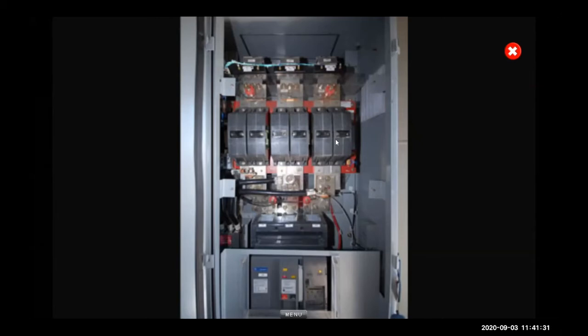And it also allows you right there, that's where they open. So if I want to turn this entire wind turbine off and not have it connected to the grid, this is where you're going to do it, guys. You're going to pull the big master switch and lock it out. That'll be the first point of isolation if you're going to be working on this.